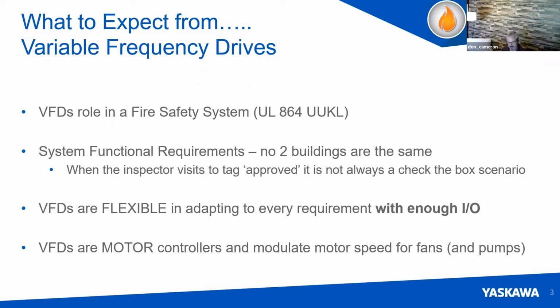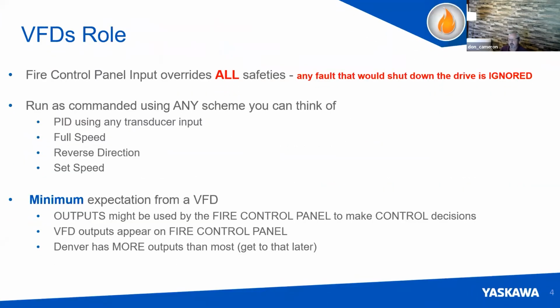And if you don't know, a drive is a motor controller, and it modulates the motor speed for fans and pumps. That's how we save energy, but in a smoke or fire situation, it's also how we can expedite the exit of smoke and create positive or negative pressure. So what does a drive, or a VFD, do in a fire control panel situation?